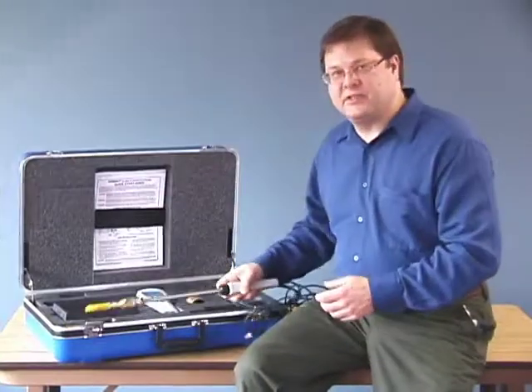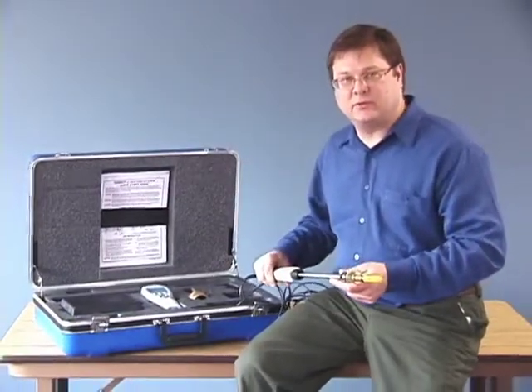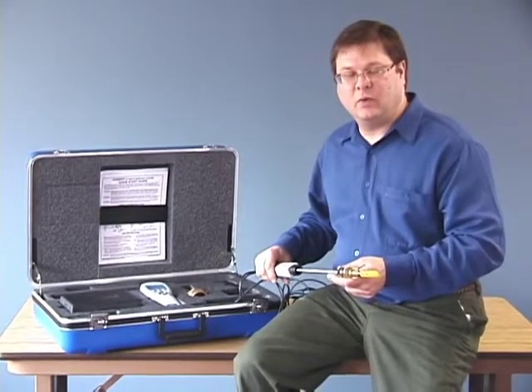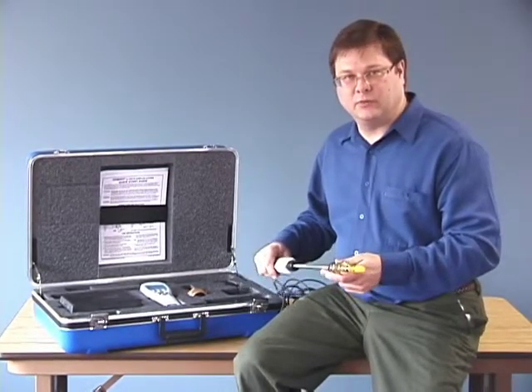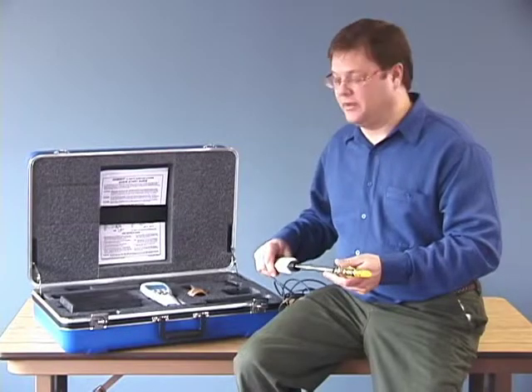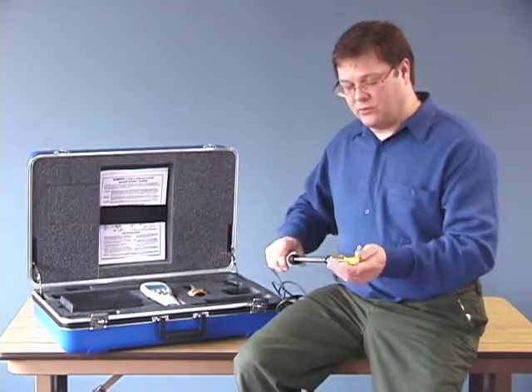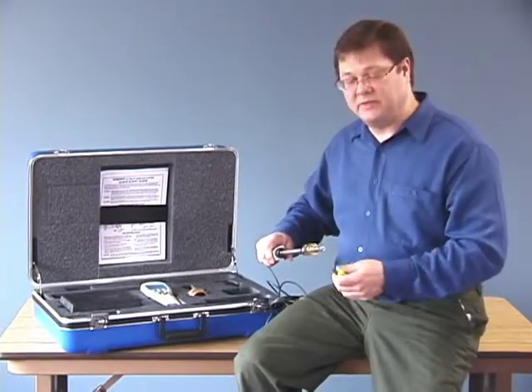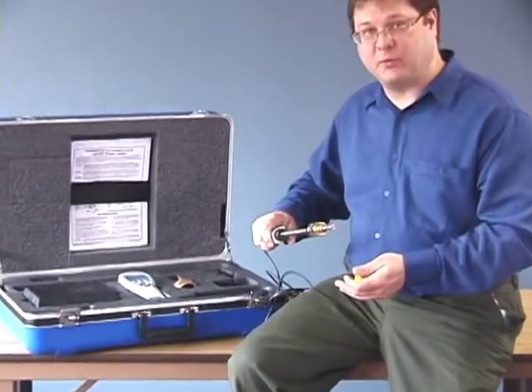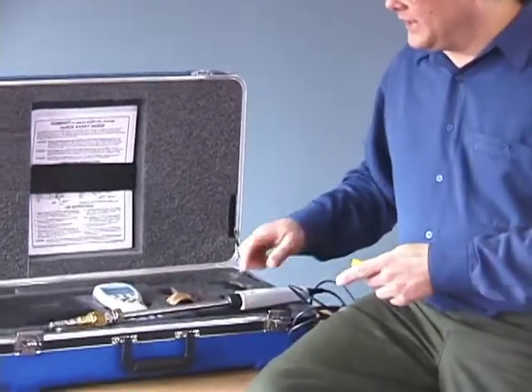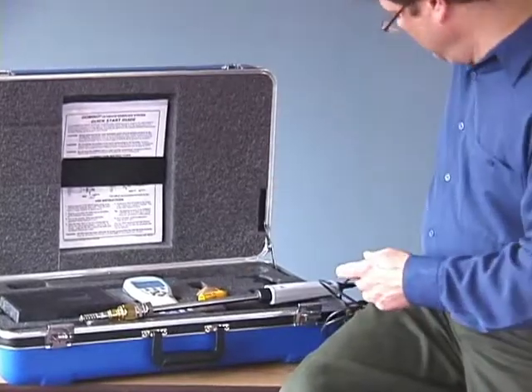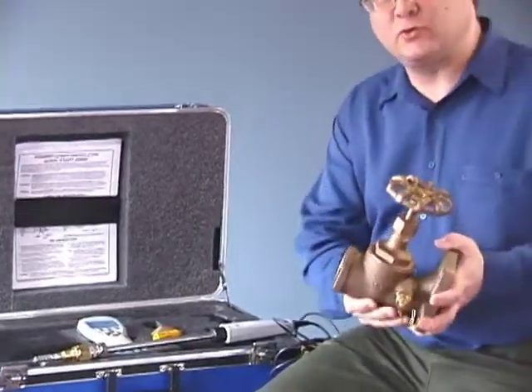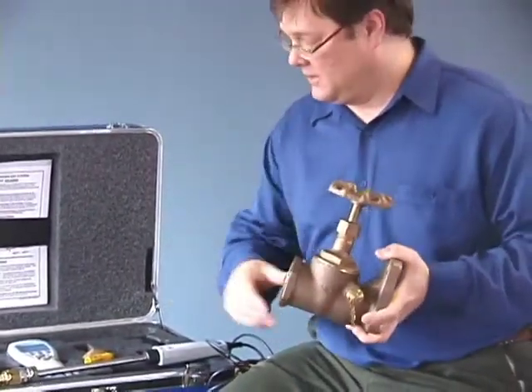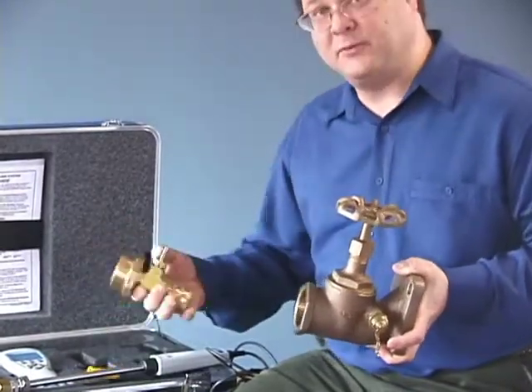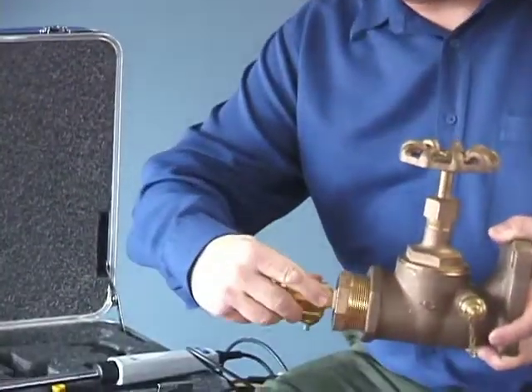The moisture and oil sensor is designed to connect directly up to a transformer drain valve, and while you're draining the oil, to read out in parts per million on the indicator. So it's actually quite simple. We take the protective cap off of the probe and get it ready. We then come up to our transformer drain valve, and we add our adapter that fits onto it after you clean it out.